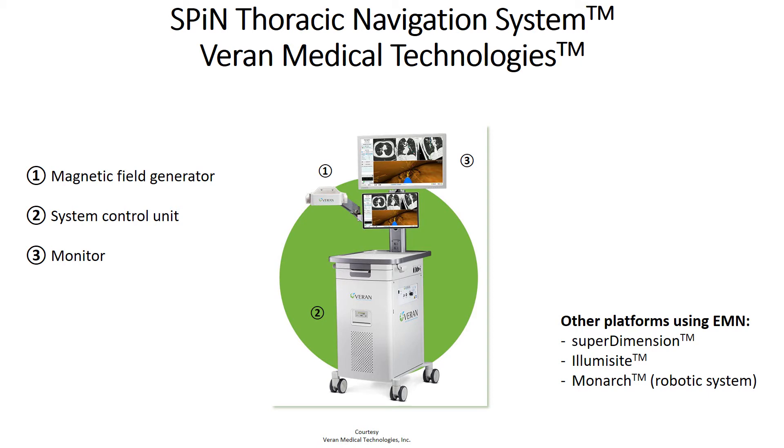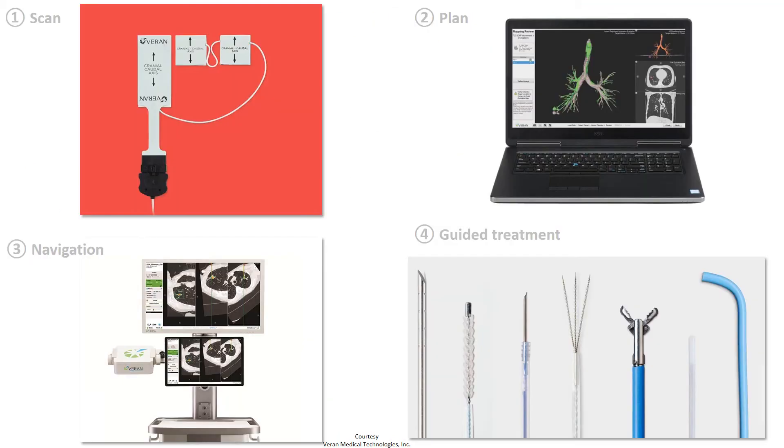The proclaimed advantages in using the SPIN thoracic navigation system are its mobile field generator and the fact that fluoroscopy is not needed when the platform is used in isolation. It also allows the proceduralist to access pulmonary lesions percutaneously. Electromagnetic navigation bronchoscopy relies on a pre-procedural CT to create the 3D airway map. After the decision is made that the patient will benefit from navigation bronchoscopy, preoperative computed tomography images are obtained and transferred to a computer, where a roadmap is generated.